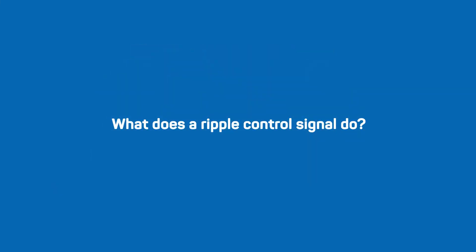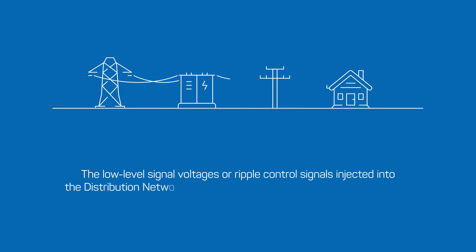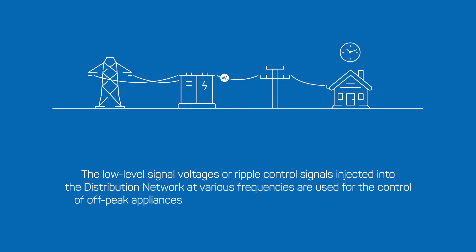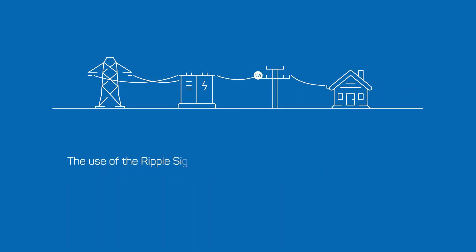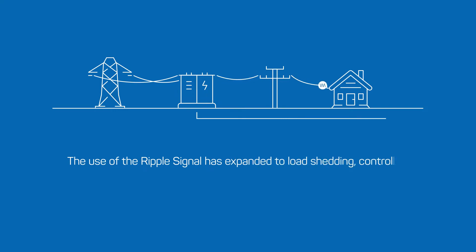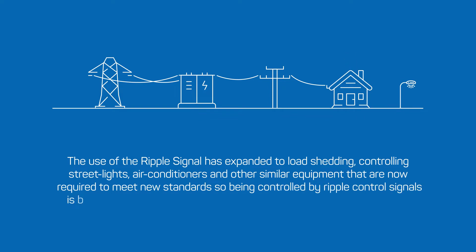The low-level signal voltages or ripple control signals injected into the distribution network at various frequencies are used for the control of off-peak appliances mainly. The signals are commonly and initially used to switch the metering for hot water and heating systems. The use of the ripple signal has expanded to load shedding, controlling street lights, air conditioners and other similar equipment that are now required to meet new standards, so being controlled by ripple control signals is becoming more popular.